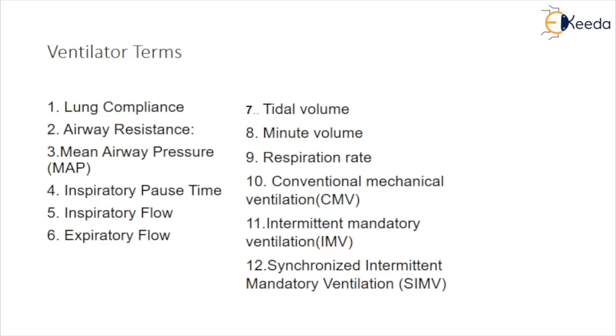Inspiratory pause time is the period of no flow when the pressure in the patient circuit and alveoli are equal. Inspiratory flow is represented as positive flow above the zero line, while expiratory flow is negative flow below the zero line. Tidal volume is the depth of breathing — the volume of gas inspired or expired during each respiratory cycle — calculated by multiplying the flow rate (liters per second) by the set inspiratory time in seconds. Calibrated tidal volume settings range from 0.010 liters to 4.8 liters; for example, a flow rate of 0.6 L/s with an inspiratory time of 1 second gives a tidal volume of 0.6 liters.